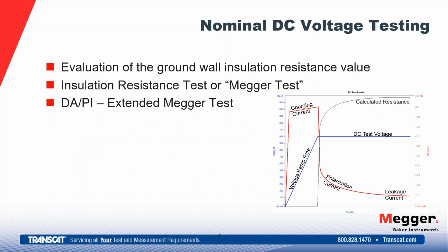The second test we talked about is the nominal DC voltage test. Here we're looking at, again, the ground wall insulation. We're going to evaluate the ground wall insulation value, the insulation resistance to ground. So we're going to apply a voltage. We're going to measure current. As we measure current, there's lots of currents involved as soon as we start applying voltage to this system. You can see the graph there to the lower right. As we ramp our voltage up, mostly what we're measuring is going to be charging current. Then we're going to let our voltage be steady.